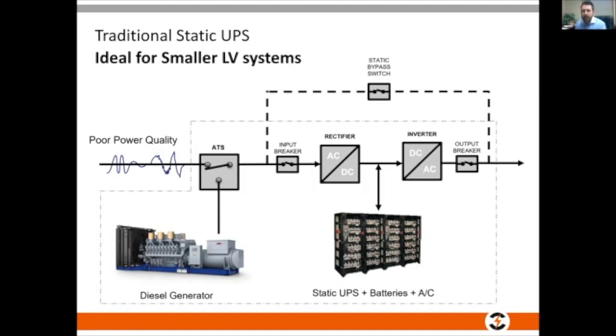And the idea here is that the batteries that are float charged will, of course, provide that interim amount of power until the diesel generator, which I show here upstream as the MTU, gets to speed. Because this diesel generator is off, it's doing absolutely nothing. It's preheated, it's pre-lubricated, and it will get to speed in about 10 seconds. Via the ATS, once the diesel generator has sped up to 1800 RPM, we will then supply power.